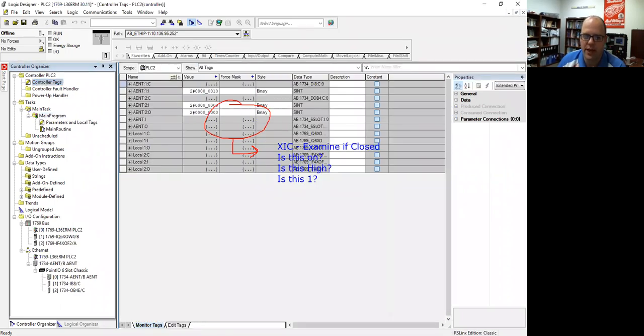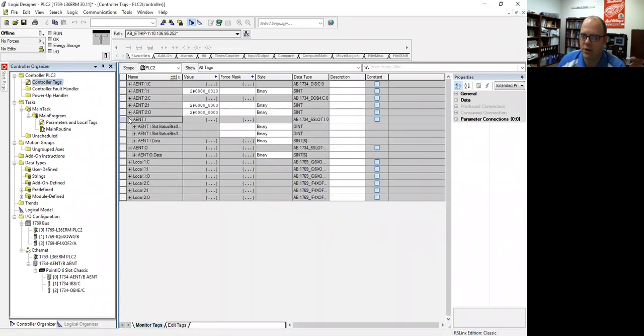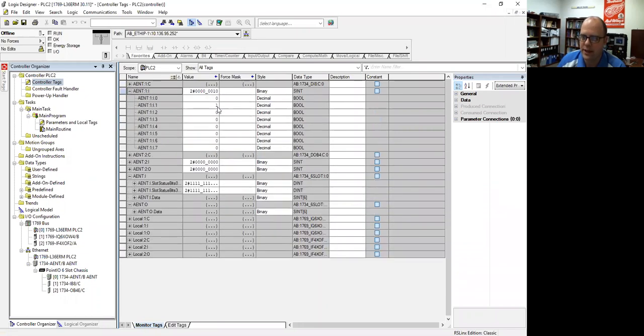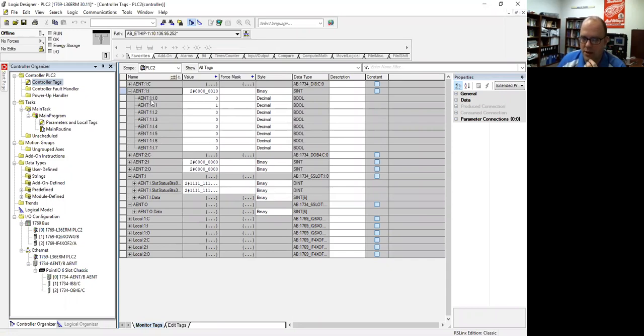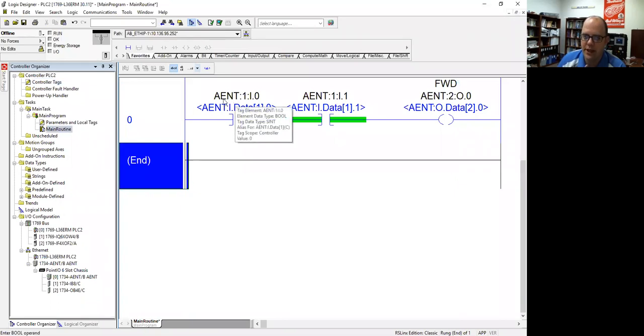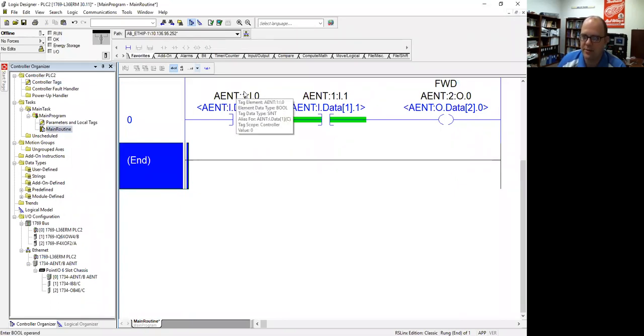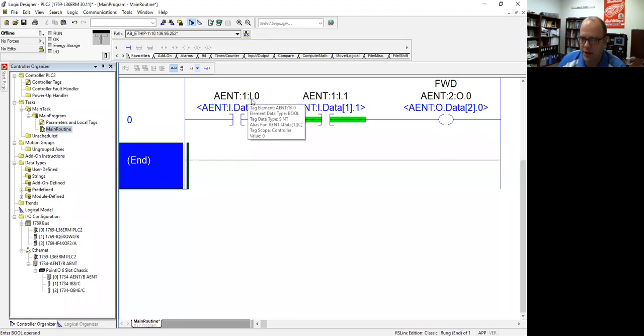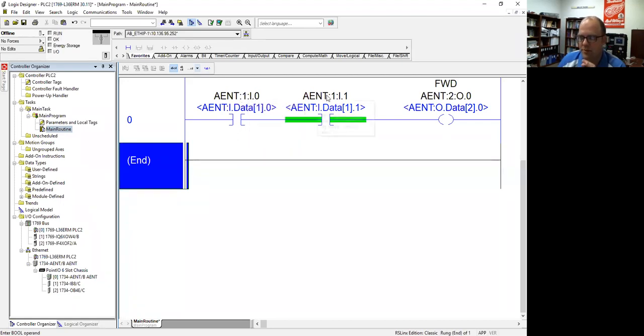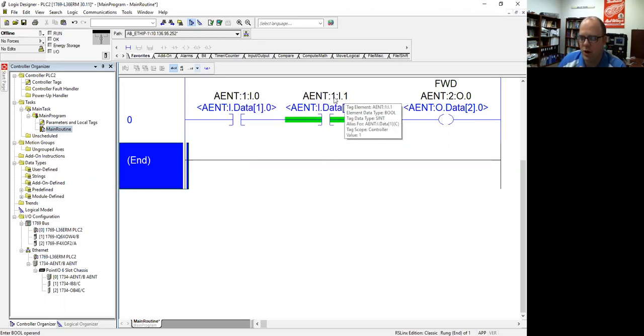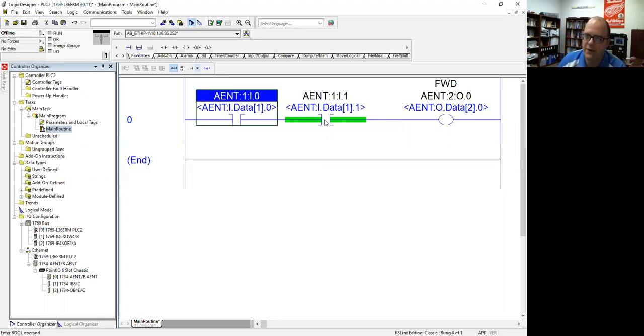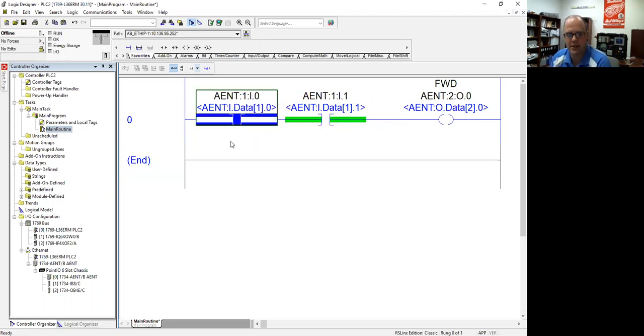And one refers to what its status is in the controller tag. So if I go into controller tags and if I look, so in this case, if I go into the input, is this a one? You can see one is a zero, one is a one, what that matches that address. Again, asking how does it connect to the processor? What slot is it? And what type of data is it? And then what bit is the screw? And you'll see it's connected via the AENT, slot one. It's an input on the zero terminal. AENT connection, slot one, one input, the one terminal. And if it's a one, it's going to be green. If it's a zero, it's going to be like this.